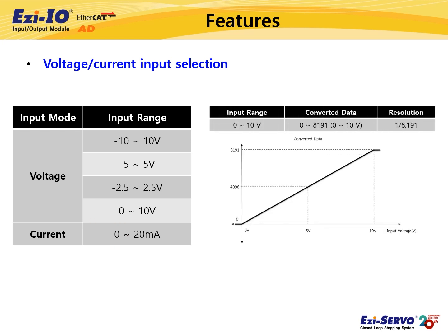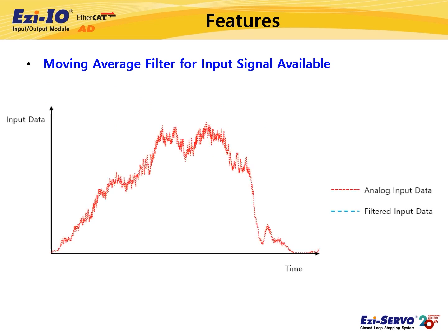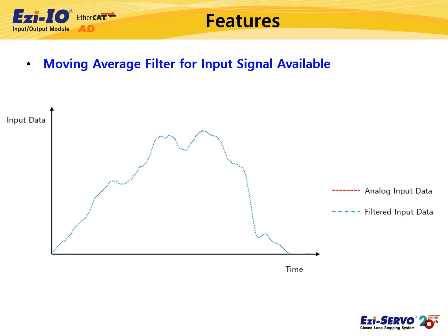Ezi-IO EtherCAT-AD converts analog input signals to digital data with a maximum resolution of 8191. For example, when the voltage input range is 0 to 10 volts, the analog input signals are converted to digital values 0 to 8191. In addition, a moving average filter is available for analog signal input to each channel. If the input analog data fluctuates significantly due to noise, the moving average filter can make the data smooth and reduce the effect of noise.